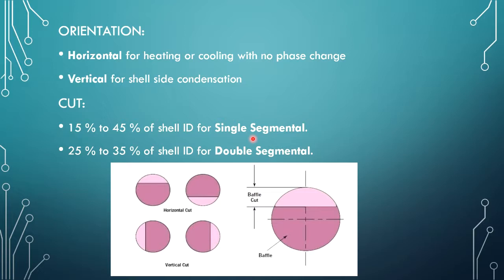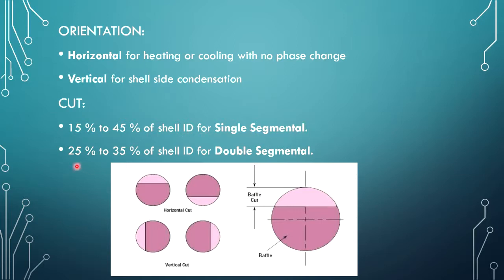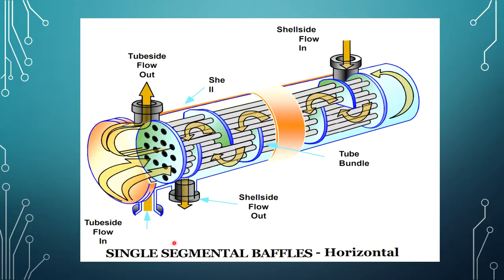Horizontal type baffles are used for heating and cooling purposes with no phase changes, and vertical type baffles are used when shell side condensation takes place. Different baffle cuts are used according to requirements: 15 to 45 percent of the shell inside diameter for single segmental baffles, and 25 to 35 percent of the shell inside diameter for double segmental baffles.